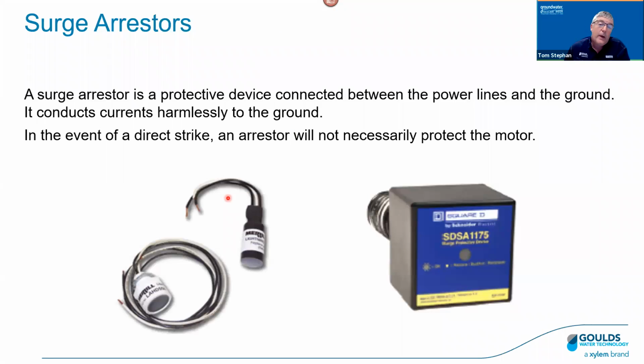A lot of people ask, can I add surge protection? And in some cases it's necessary because of the presence of lightning and surges. And so yes, certainly you can. Normally though, no matter what you have, if there's a direct strike, you might still have some issues. But here's a couple examples of some additional surge arresters. The one on the right is fairly new for us, and the one nice thing about it is it's got a light right there that indicates that if it's on, it's working, and if the light is off, there's an issue. Maybe it got hit and took it out, and so we need to replace that.